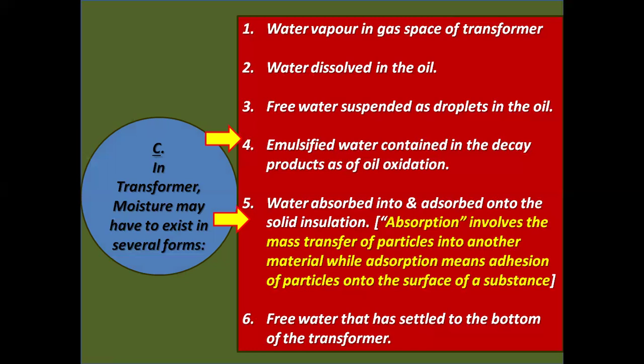Water vapor in the gas phase of the transformer, in the solid insulation part. Number two, water dissolved in the oil. Number three, free water suspended as droplets in the oil. Number four, emulsified water contained in the decay products of oil oxidation. Number five, water absorbed into or adsorbed onto the solid insulation. Absorption involves the mass transfer of particles into another material, while adsorption means adhesion of particles onto the surface of a substance. Number six, free water that has settled to the bottom of the transformer.